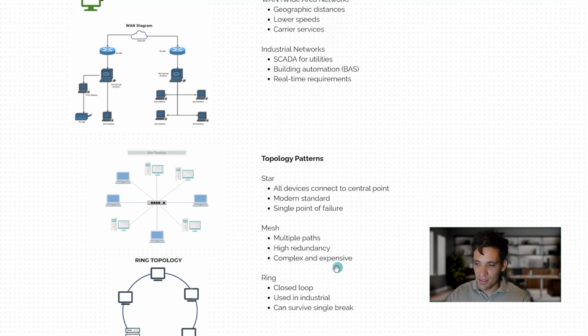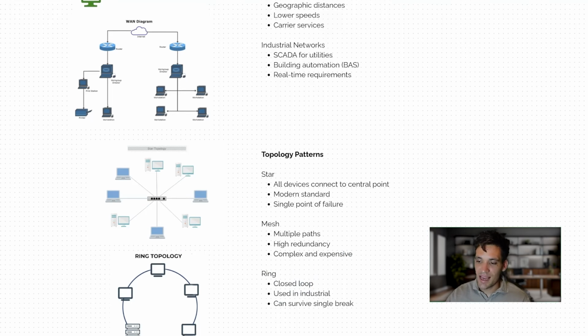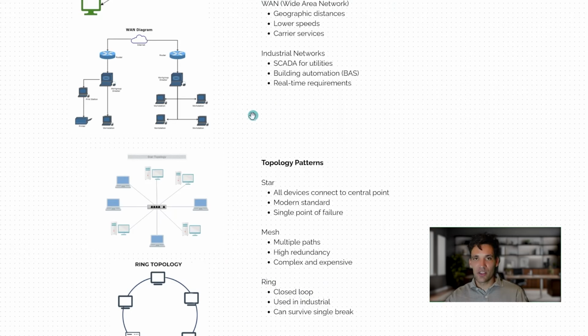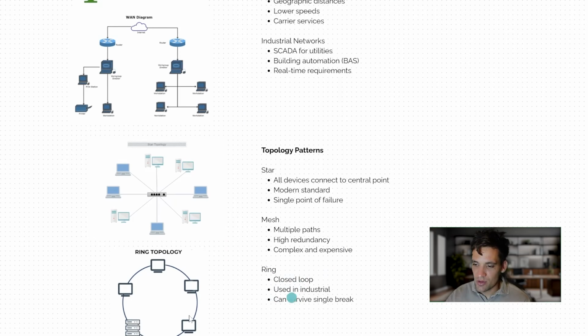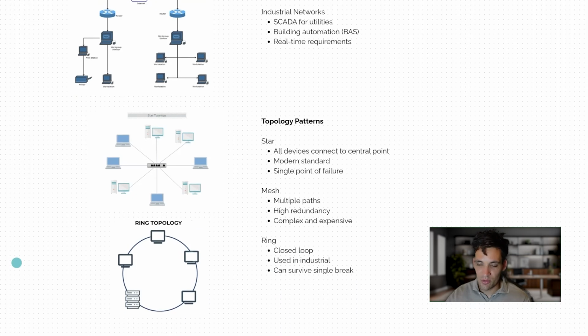That fails, you lose everything. You can have a mesh topology, which is where everything's interconnected, but you have much more redundancy. But again, because you've got more equipment, more cables you're running, it's complex and expensive. Or you can have a ring topology, which is what you see on most industrial networks, where you have a closed loop. So for example, if that cable fails, there's two routes to that device. It can go and route through the other way.